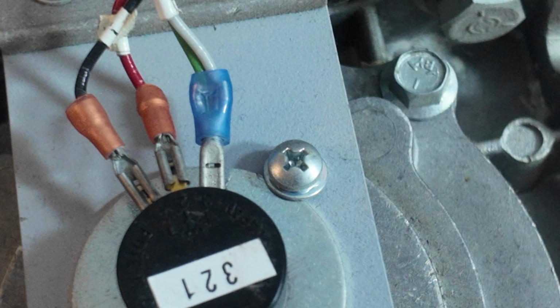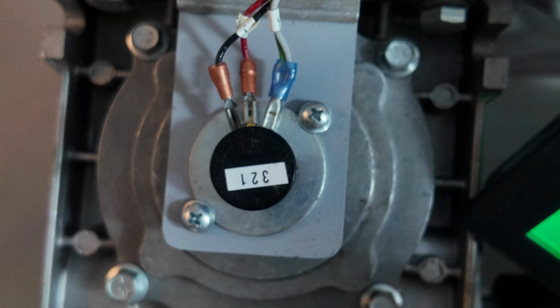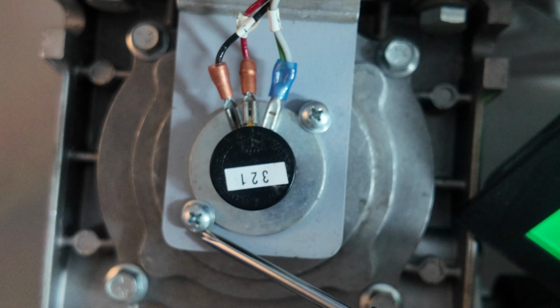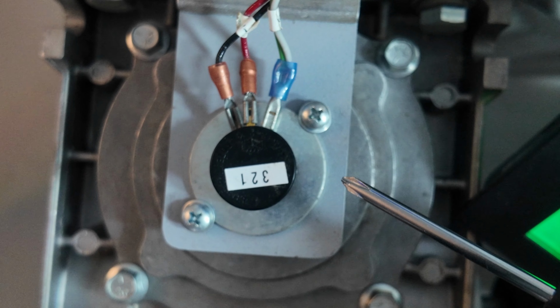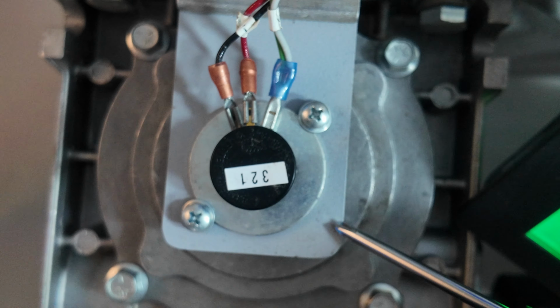Shifting, inconsistent, or moving door position. If you find that the hard closed door position with the door up against the frame is shifting significantly on each cycle or over time, then the transducer is physically shifting due to not being secure. There are 3 locations to check: the 2 locking screws on the top of the bracket, the small set screw in the shaft of the worm gear.